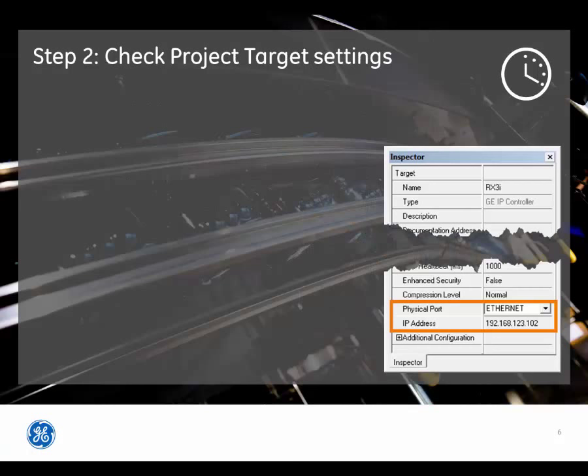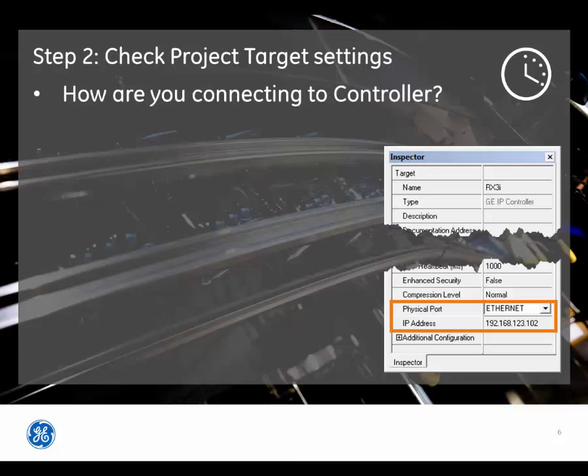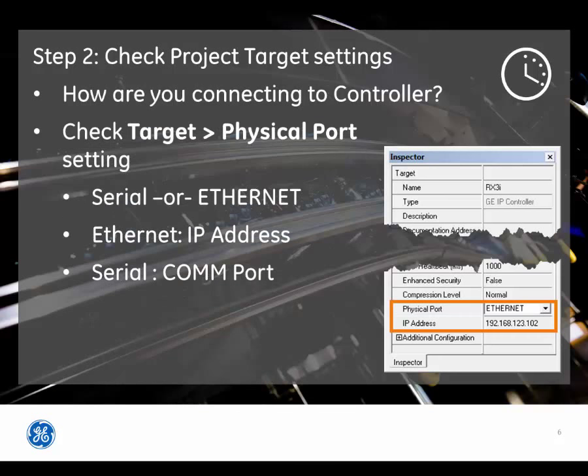For Step 2, check the project target settings to answer the question: How are you connecting to the controller? Check the target physical port setting to verify that it is set to serial or Ethernet to match your setup. If Ethernet, make sure the IP address matches the IP address of the controller. If serial, make sure the correct COM port is selected.